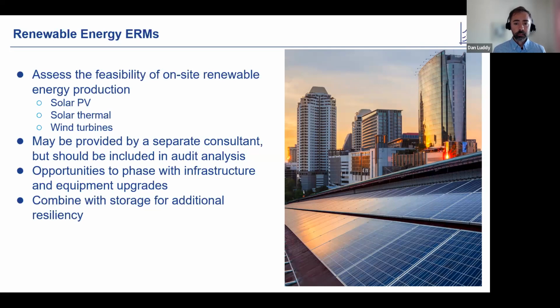That information and assessment should be communicated to the auditor so they can include it in their analysis, and view it at the same time as all these other possible emissions reduction measures. It's an opportunity to phase in any retrofits you're doing to incorporate that renewable energy system. If you have to upgrade your electrical service to tie in this PV on the roof, it's also a great time to make sure you have enough capacity for future heat pumps or EV chargers, and just do that electrical service upgrade once and do it right.